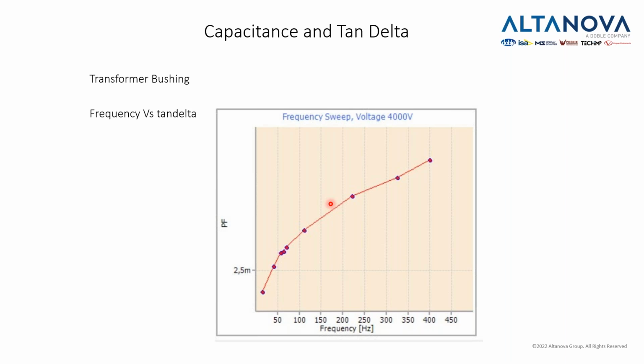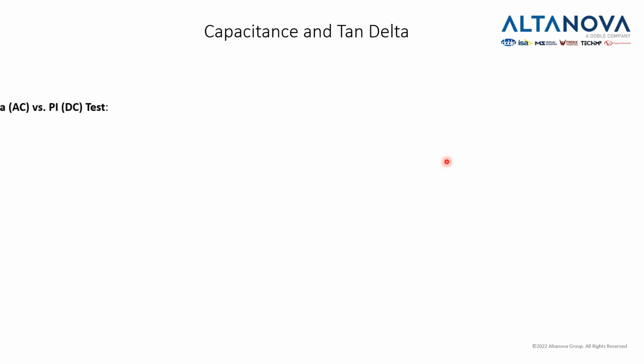And we can also have a variable frequency, and this is more or less done quite often on the bushings if they show us some issues with the value that we measure. So here we see that as we increase the frequency, the power factor or tan delta also increases, and this delta, the change of power factor or tan delta, is also defined. So it can change, but not much. It should change a little bit, but not much.